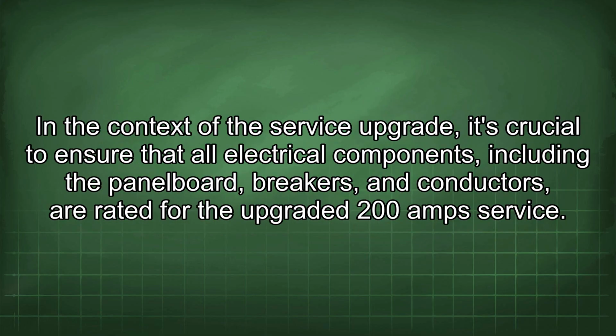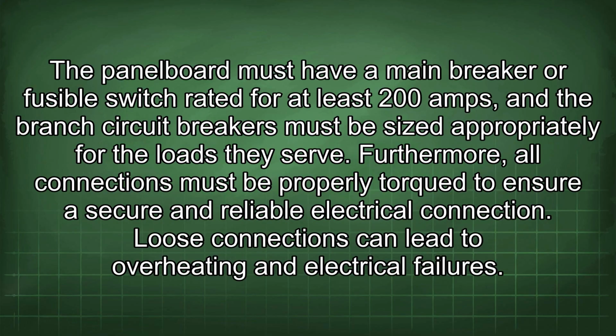In the context of the service upgrade, it's crucial to ensure that all electrical components, including the panel board, breakers, and conductors, are rated for the upgraded 200 amp service. The panel board must have a main breaker or fusible switch rated for at least 200 amps, and the branch circuit breakers must be sized appropriately for the loads they serve. Furthermore, all connections must be properly torqued to ensure a secure and reliable electrical connection. Loose connections can lead to overheating and electrical failures.